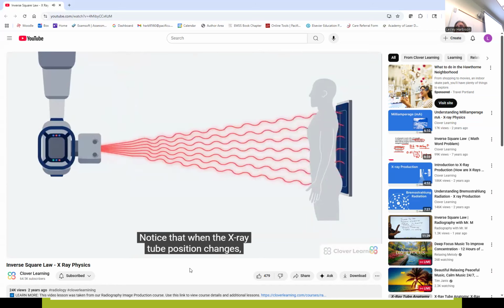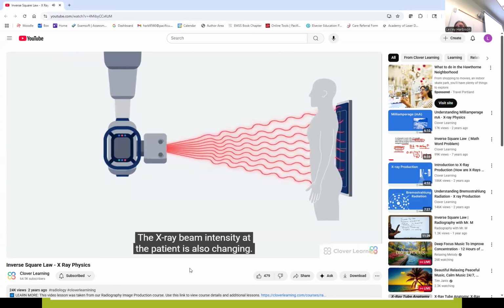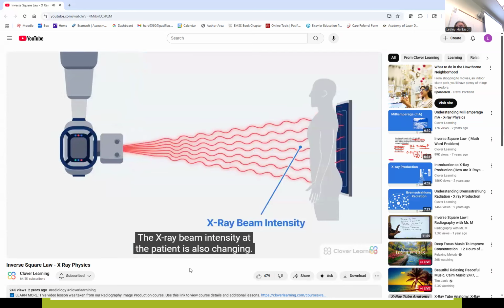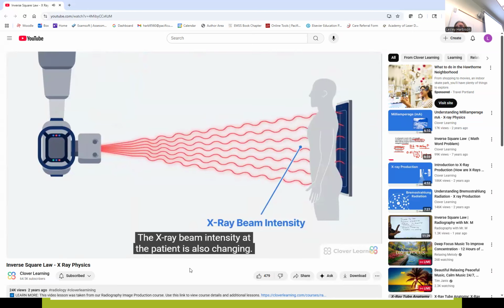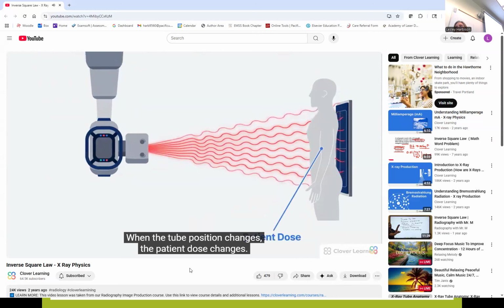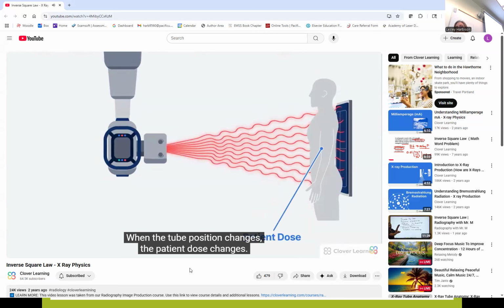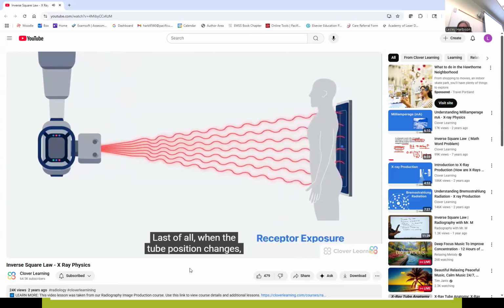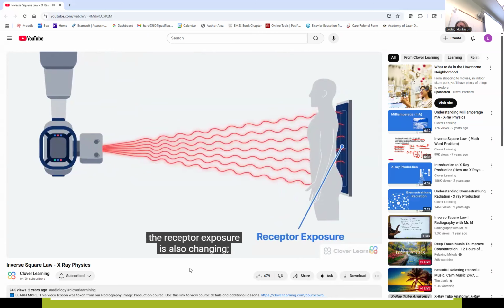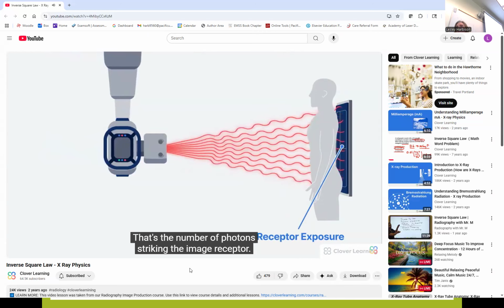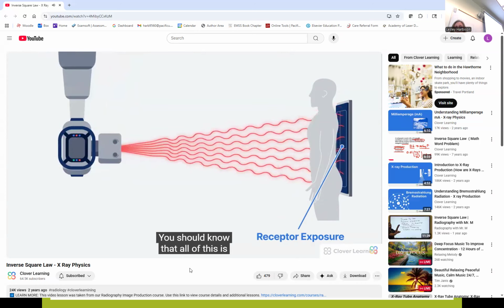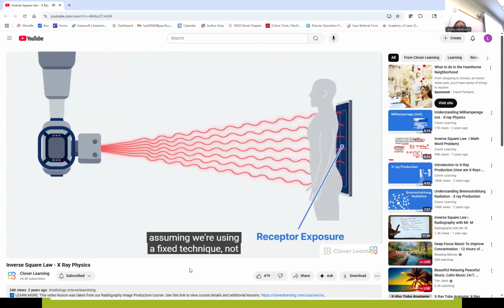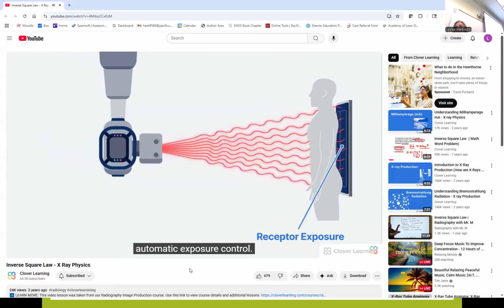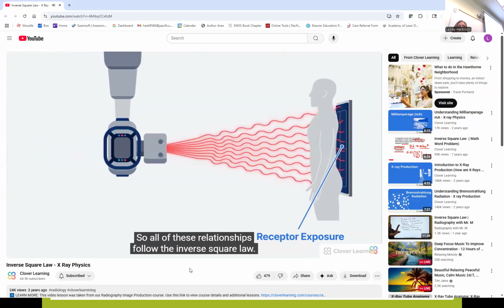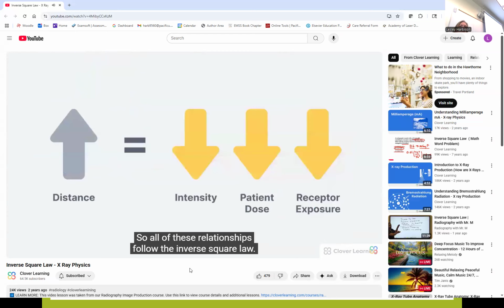Notice that when the X-ray tube position changes, there's several other variables that change. The X-ray beam intensity at the patient is also changing. When the tube position changes, the patient dose changes. And last of all, when the tube position changes, the receptor exposure is also changing. That's the number of photons striking the image receptor. You should know that all of this is assuming we're using a fixed technique, not automatic exposure control. So all of these relationships follow the inverse square law.